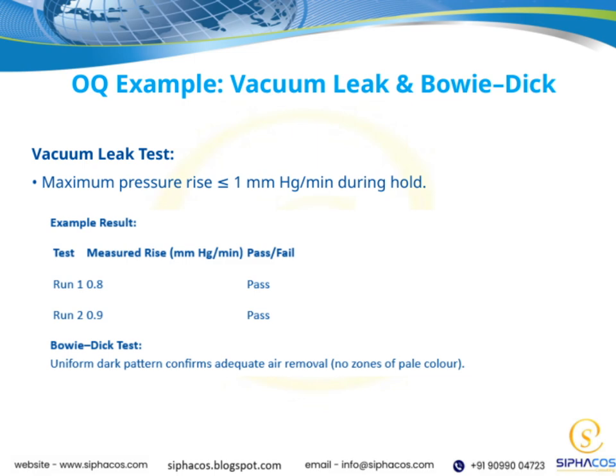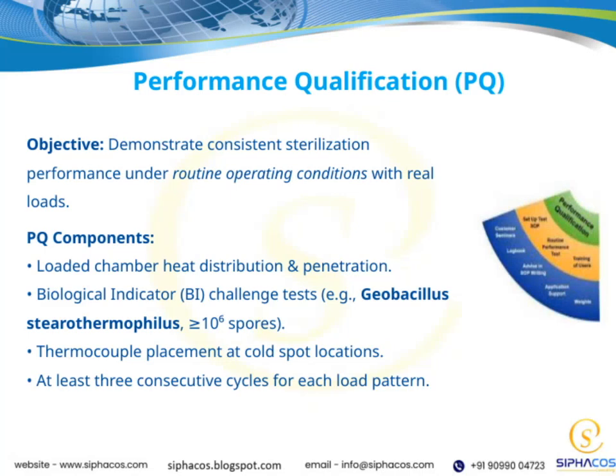Ensuring this parameter is within limits is essential for validating the integrity of our sterilizer's vacuum cycle. Remember, maintaining this standard helps us ensure that our sterilization process is effective and safe. This example ties into the overall theme of quality assurance and the importance of routine testing to prevent issues before they impact patient safety. Let's talk about performance qualification, or PQ.